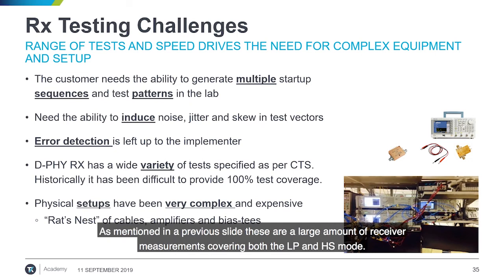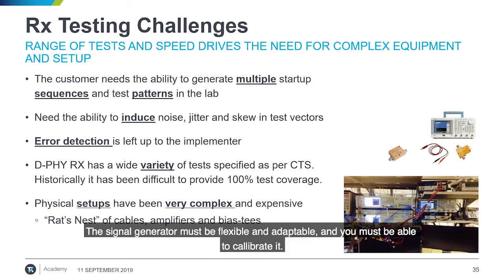As mentioned previously, there are a large number of receiver measurements covering both the low power and HS modes. The signal generator must be flexible and adaptable, and you must be able to calibrate it.